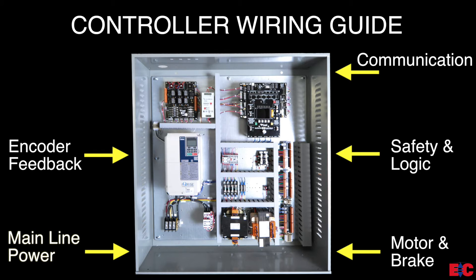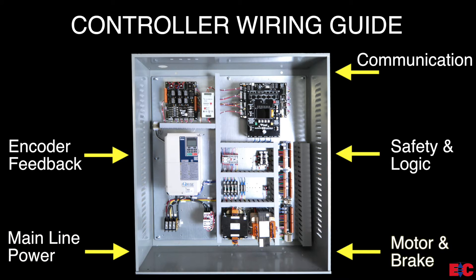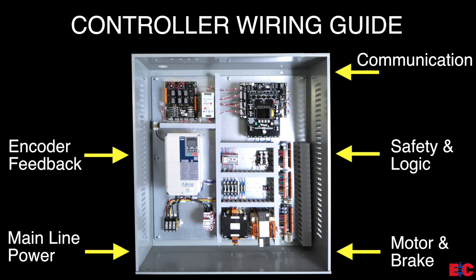Starting from the lower left, mainline power, which includes line power and ground from the elevator disconnect. Next on the lower right, we have the motor and brake, which includes power wiring to the motor, brake, and ground. Note that both the motor wiring and mainline power knockouts can be interchanged in use.